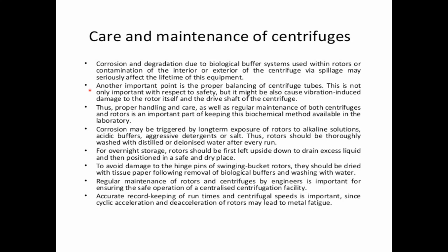And I remember a case where a centrifuge has exploded. Nowadays, centrifuges have built-in safety measures that when a bit of vibration is sensed in the centrifuge, it stops immediately.